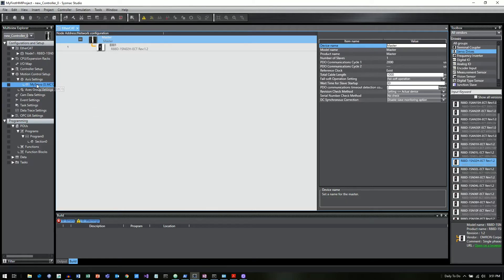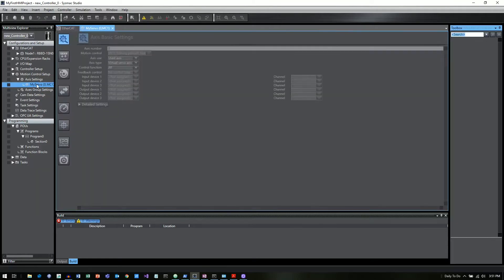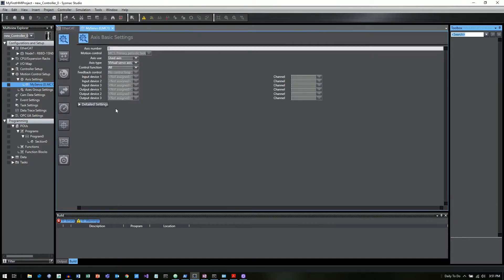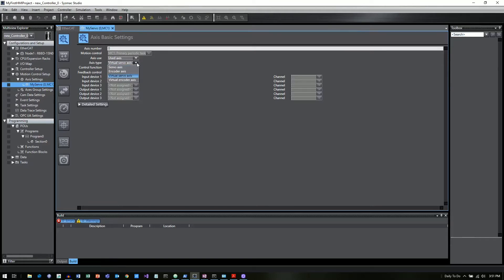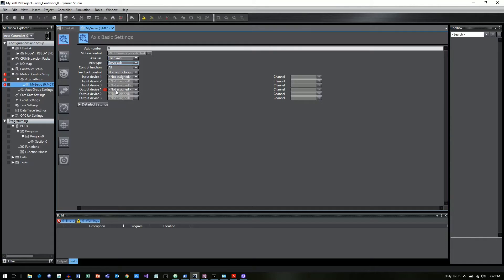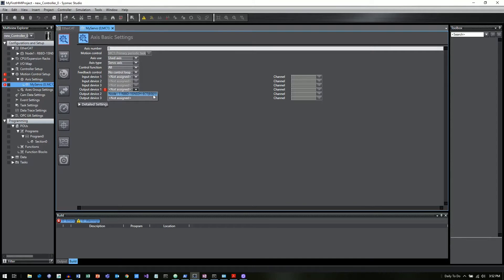And if you double click on that, it will open up the settings. And what we need to do then is actually assign this motion control axis to the EtherCAT node, the servo that's assigned to that EtherCAT node. So we need to change the axis type from virtual servo axis to servo axis and then you'll see a red exclamation point down here under output device and for that you click on that drop down and it's going to give you a list of applicable EtherCAT nodes that are out there.